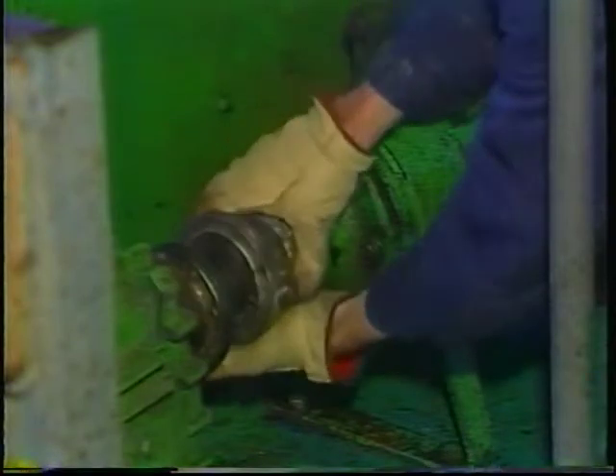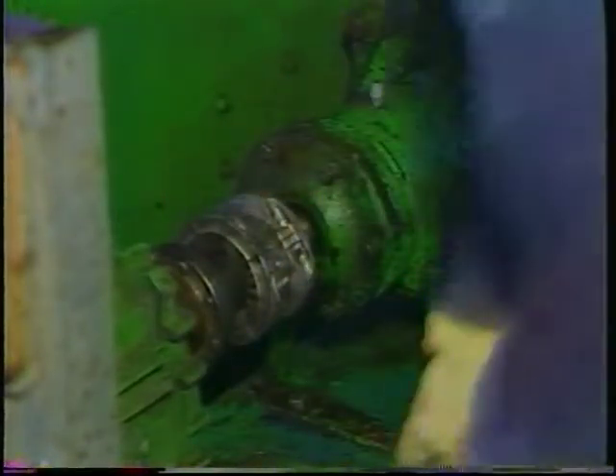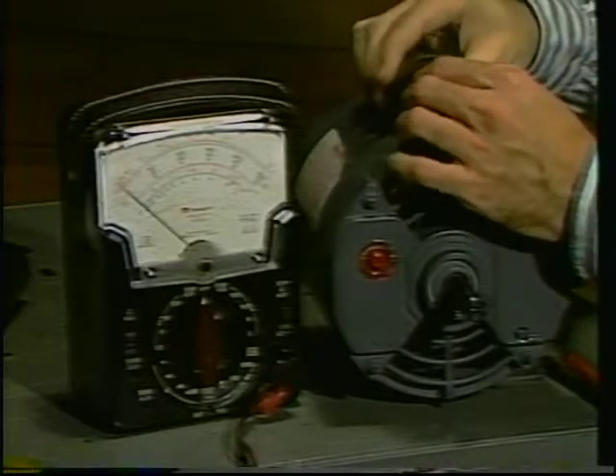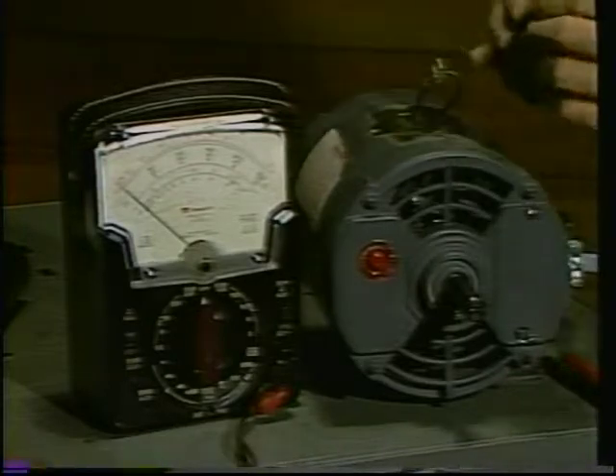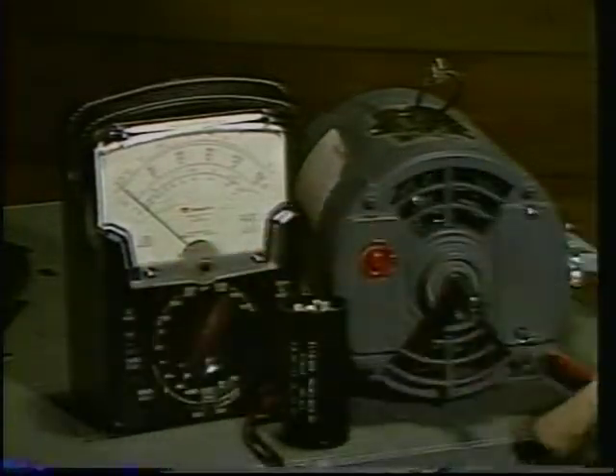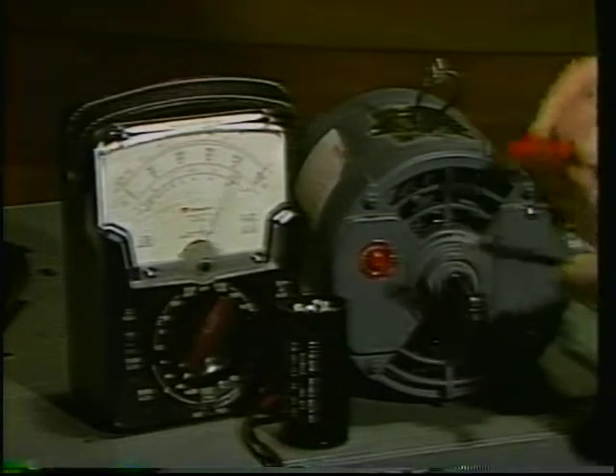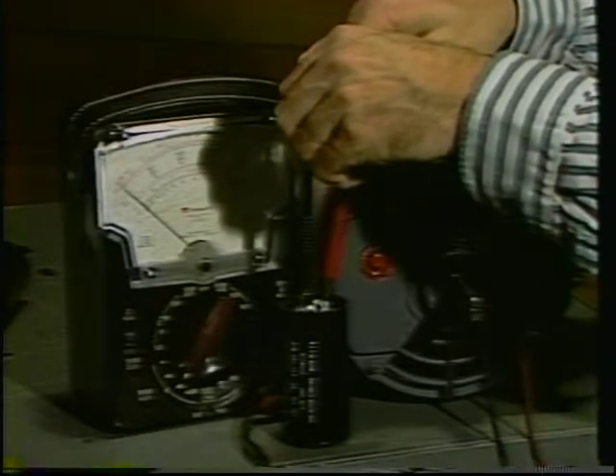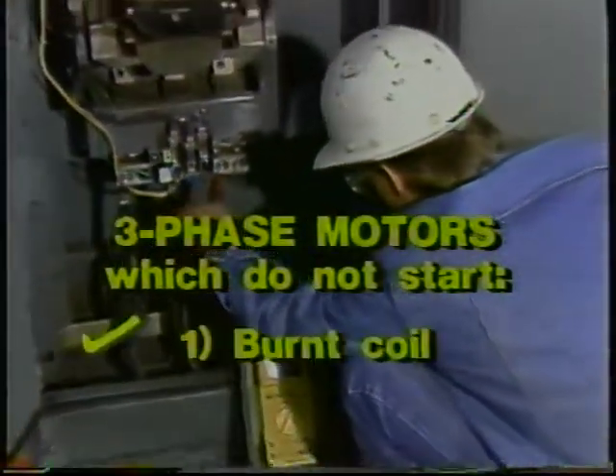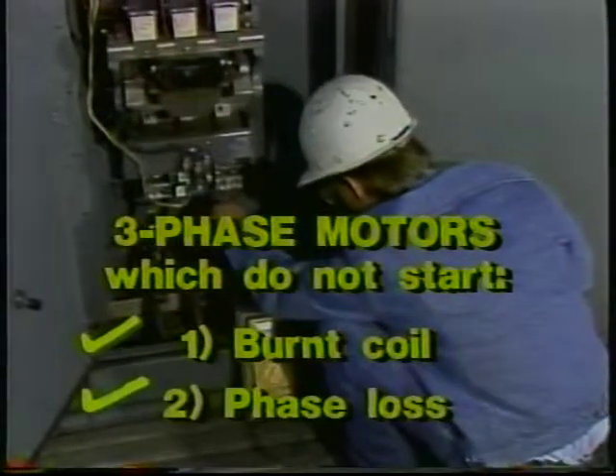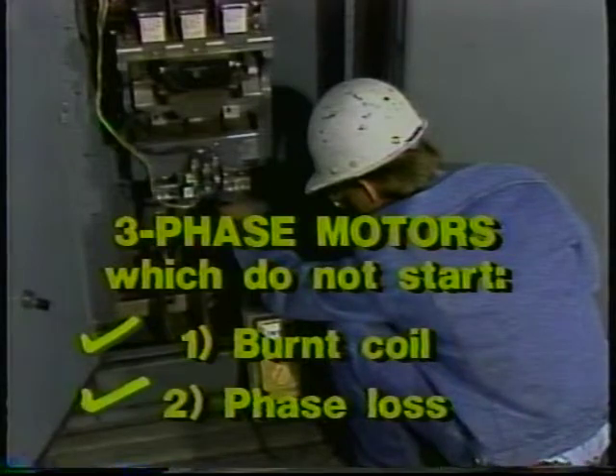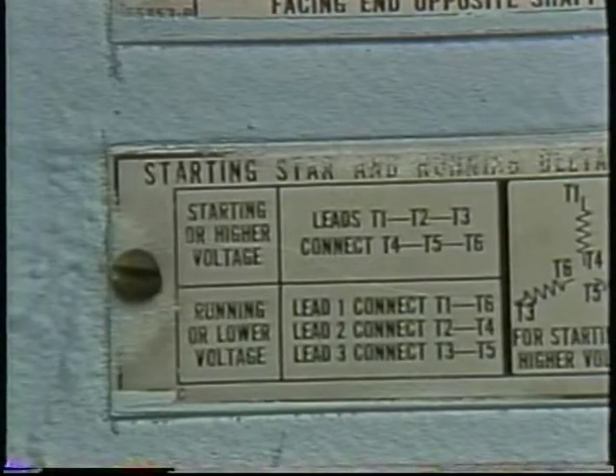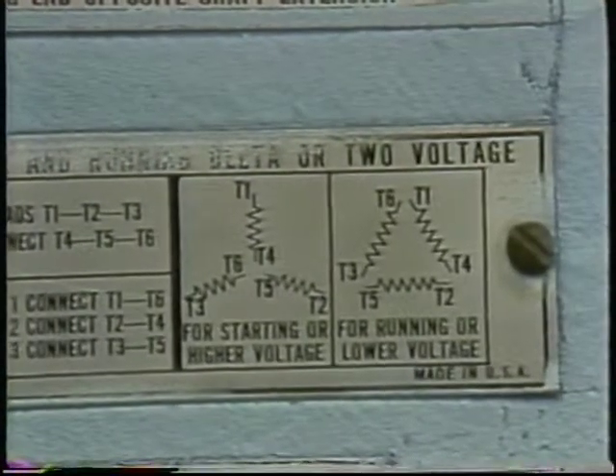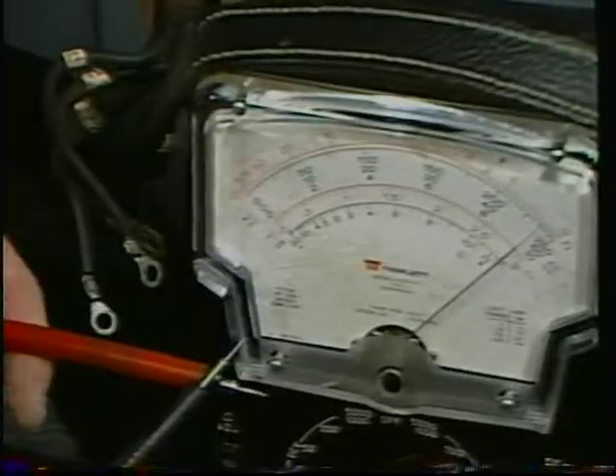If there is no jam-up and the coupled shaft will turn, the cause of the problem can vary depending on the type of motor. A single-phase motor that will not start up may have a problem somewhere in the starting circuit. The start winding may be burned out, or the centrifugal switch may not be closing. A capacitor may be shorted or open. Resistance readings should pinpoint the problem. A three-phase motor, induction or synchronous, that will not start up at all may have a burned-out coil. Or one-phase voltage may be zero. Voltage and resistance checks will eliminate one or the other possibility. Be sure you know how the motor is connected internally. An open winding may not show up in a delta motor. A DC shunt motor with an open in the field circuit will probably not start up under load.